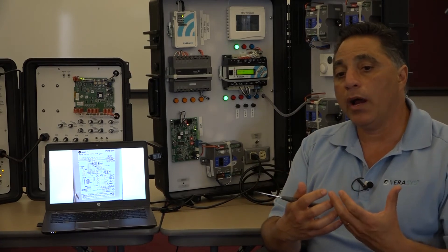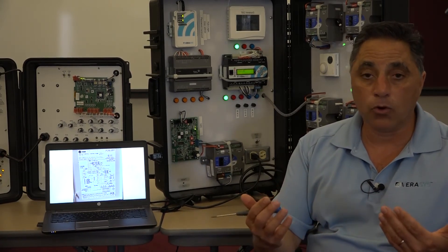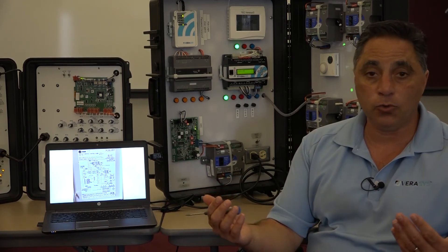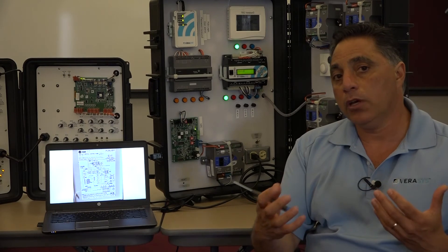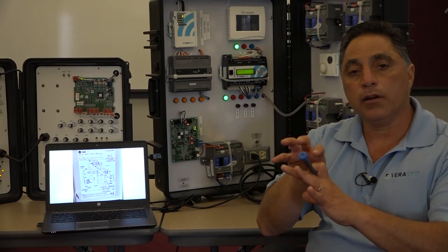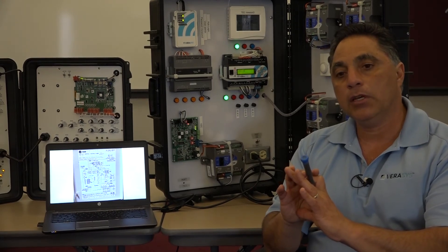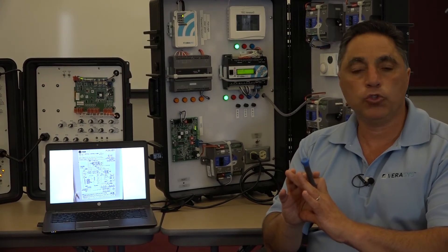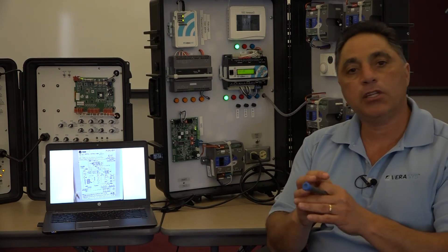You reuse the wire from a communication perspective. You reuse the wire from a power perspective. Again, you don't have to run any new power. Same 24 volts works for us. And the only other thing you would have to do is that the gear that sits on top of the shaft for the damper movement is very short.